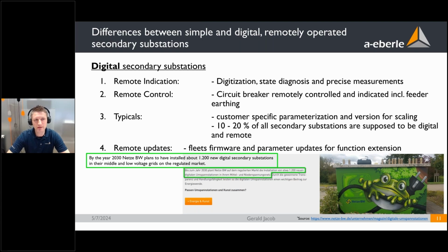Third topic here is the topic typicals or standards. So we are talking about thousands of secondary substations in the field. We are not talking about primary substations where you are going with a lot of people and doing commissioning individually, but you need to have standards because you want to install, for example, one secondary substation per day, and therefore the parameters and the delivery of the devices have to be fixed, have to be standardized.